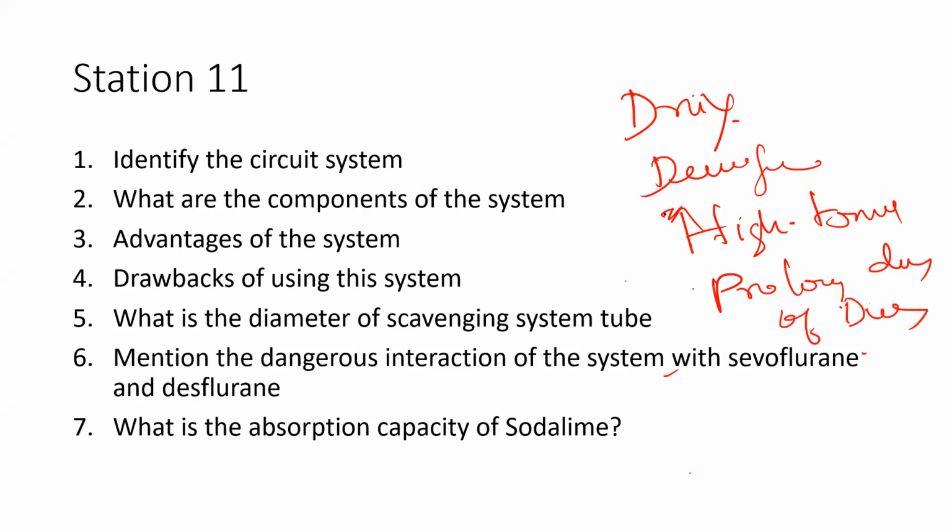So these are the 4 situations where you can get chances of developing compound A with sevoflurane, or carbon monoxide with desflurane. When the soda lime is dry, when the soda lime is desiccated, when the temperature in the soda lime is very high, and when you use a prolonged duration of low flows of anesthesia. Okay, good. What is the diameter of this scavenging system?